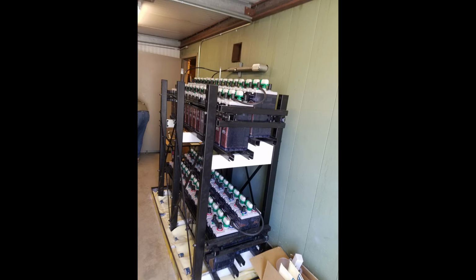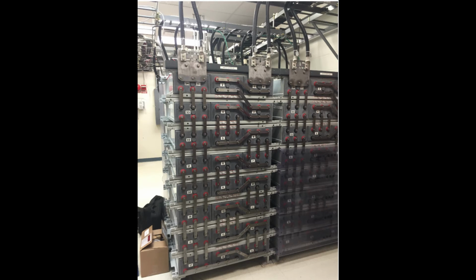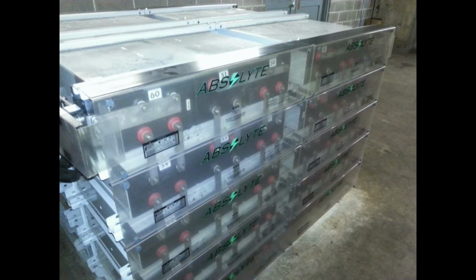For this example, let's assume that this is a 60-cell lead-acid battery that is being floated at 135 volts, and that this is a perfect world, and this system normally measures 67.5 volts on each end of the battery. This would be a typical power plant or substation or switchgear type arrangement. There is a ground alarm, and you have to locate it and take appropriate action.